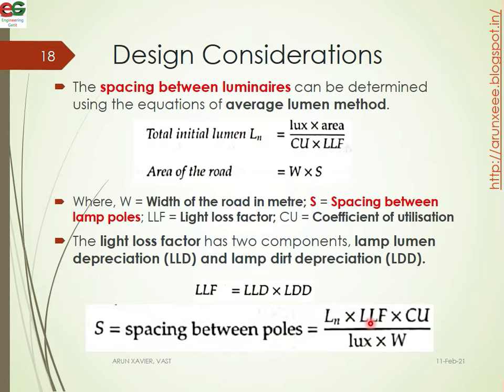LLF means Light Loss Factor. The Light Loss Factor has two components: first is Lamp Lumen Depreciation (LLD), and the second is Lamp Dirt Depreciation. So the spacing equation is: S equals LN times LLF times CU divided by lux times W, where W is the width of the road.